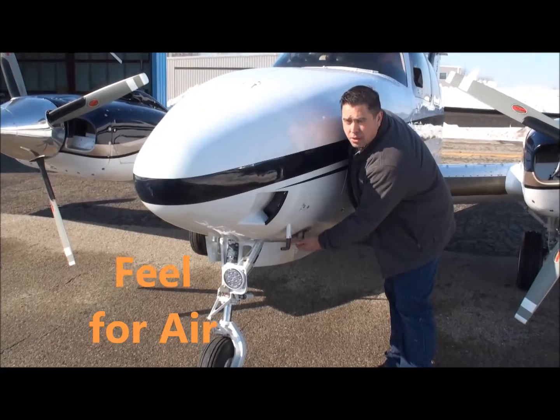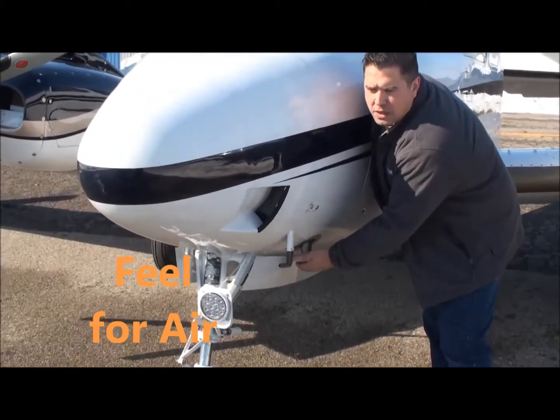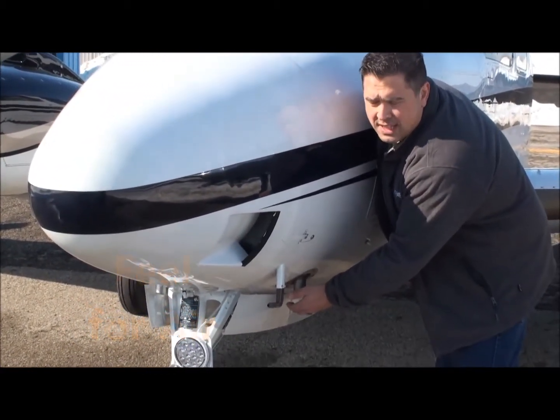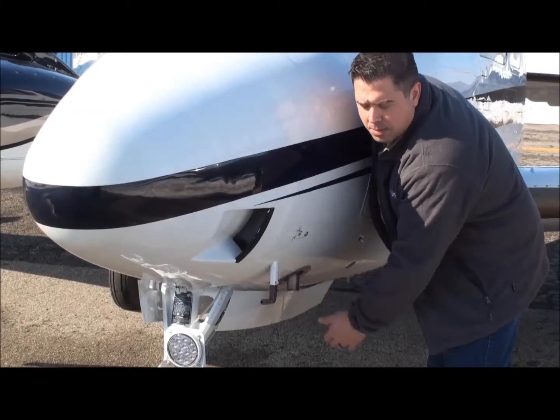So right now I'm feeling for combustion air. It needs combustion air to burn. And the combustion air should feel like a hairdryer on low. You should have at least that much airflow coming from that blower or something.